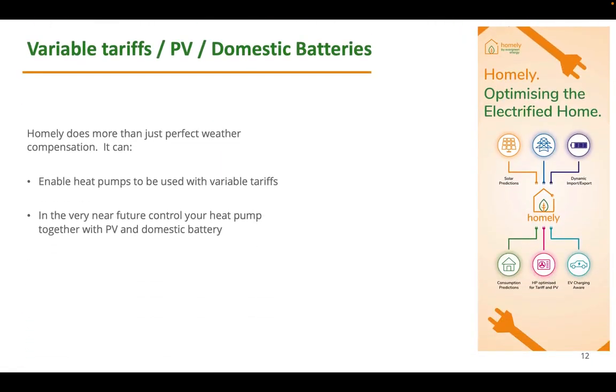Now, Homely is more than this. So Homely can actually, in addition to delivering this perfect weather compensation for customers where they have just a single rate tariff throughout the day, also take into account variable tariffs, such as Octopus Go, Octopus Agile, other EV tariffs where the electricity price is cheaper overnight, and overlay what we know about the house and what we know about the different efficiency of different flow temperatures with the electricity prices. So for example, make a decision that it makes more sense for this house to actually heat at slightly higher flow temperatures in the middle of the night, even though it's colder outside.